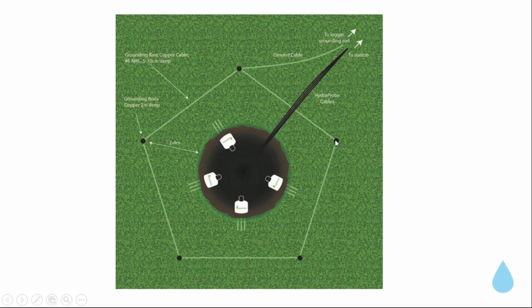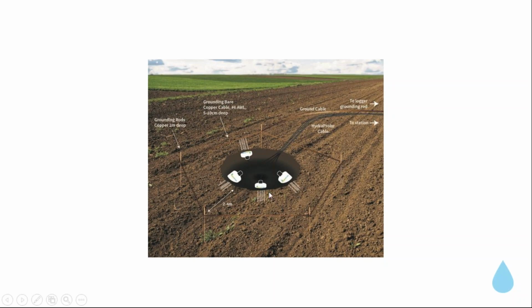Actually, two or three automotive hose clamps to connect these cables, and you can bury this. The cables connecting the ground rods can be buried a couple centimeters underground so no one trips over them. Then it can all be connected to a single grounding cable run back to your logger station. Here's another 3-dimensional diagram of protecting the soil profile with your grounding rods going 2 meters deep, and the cable connecting all the rods going back to the logger station.